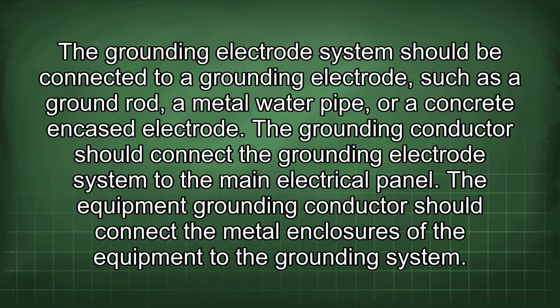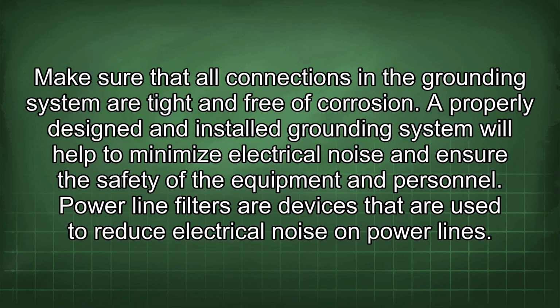The grounding conductor should connect the grounding electrode system to the main electrical panel. The equipment grounding conductor should connect the metal enclosures of the equipment to the grounding system. Make sure that all connections in the grounding system are tight and free of corrosion. A properly designed and installed grounding system will help to minimize electrical noise and ensure the safety of the equipment and personnel. Power line filters are devices that are used to reduce electrical noise on power lines.